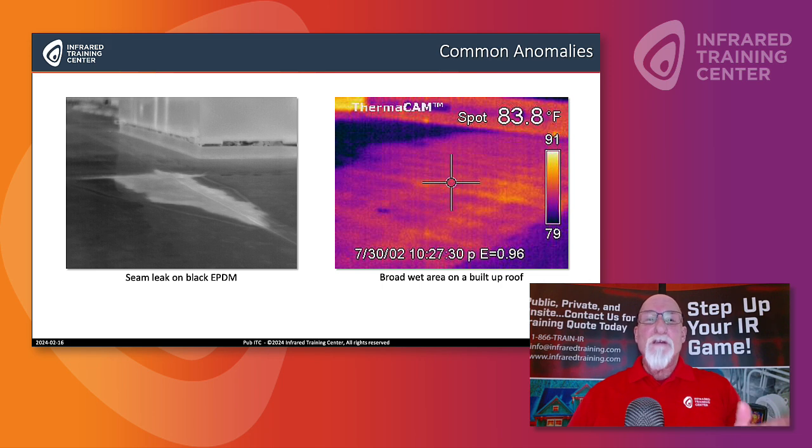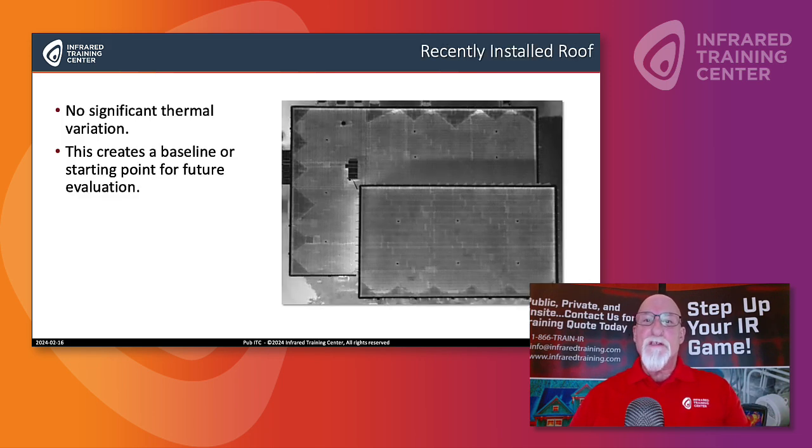Now, baseline study. I've been hired many, many times by roofing companies that actually put down the roofing materials. What they want to do is prove to the customer that the roof is fine. They also want to be able to have me or another thermographer go up yearly and do an inspection of the roof. What we want to do is make sure that the roof is not failing. Better to catch it early than too late. And so that baseline is very important to take images.